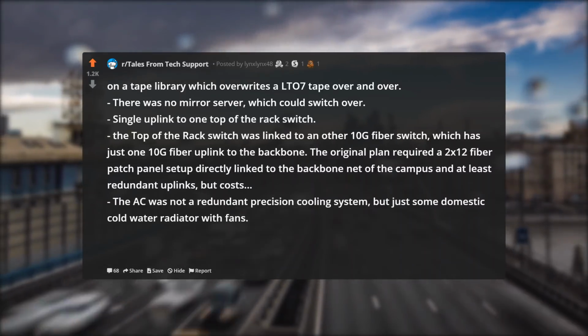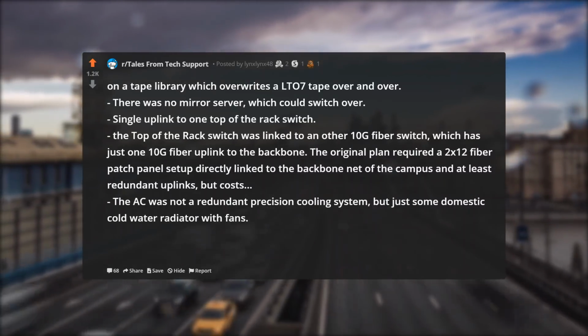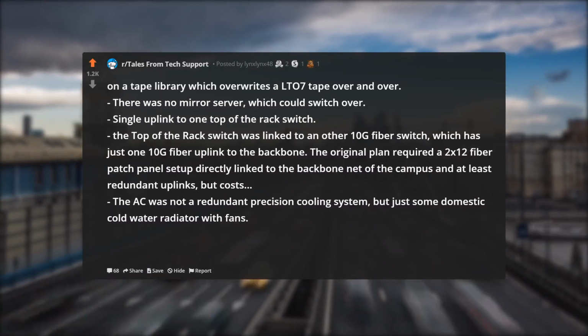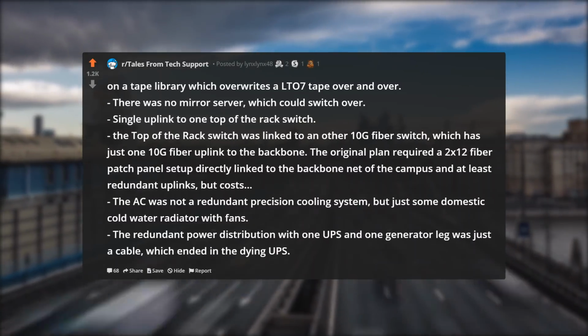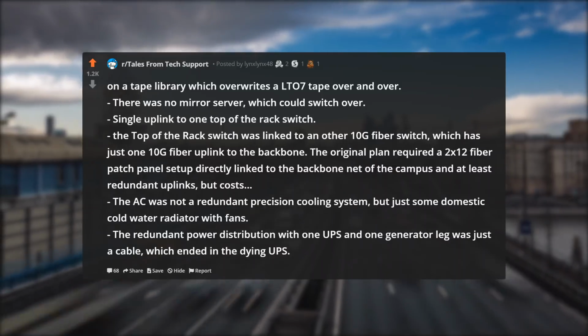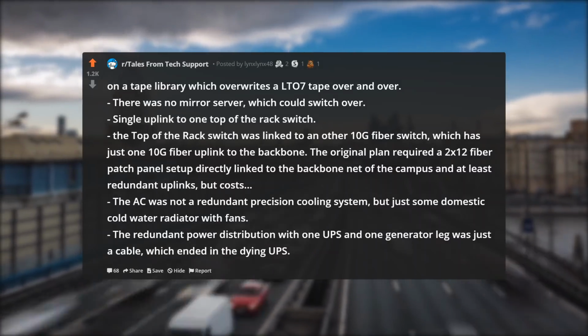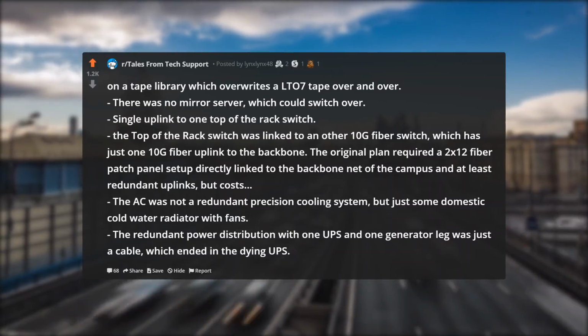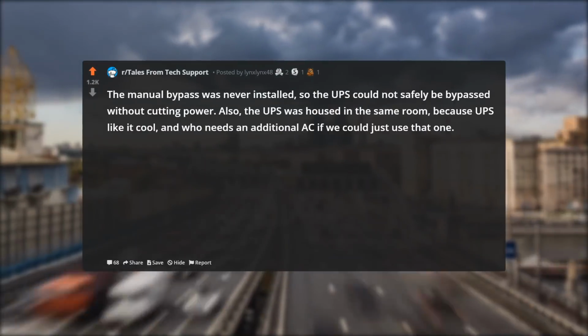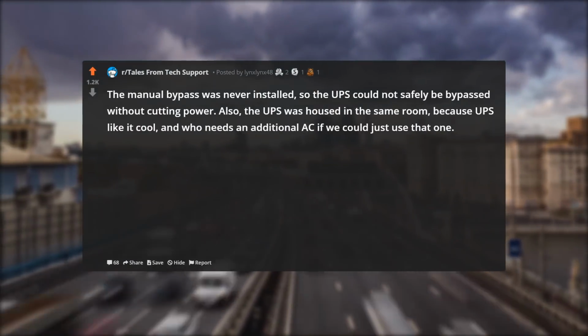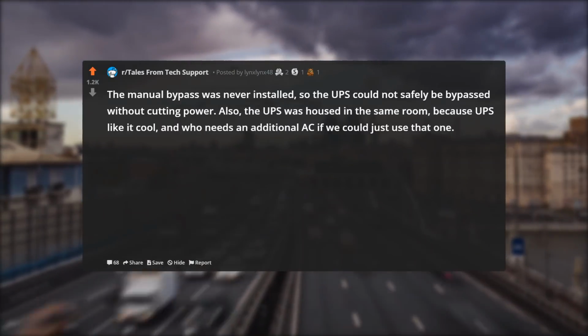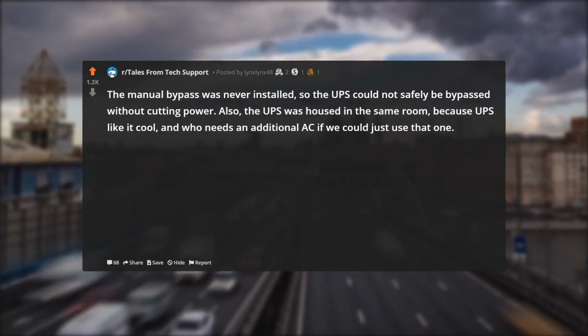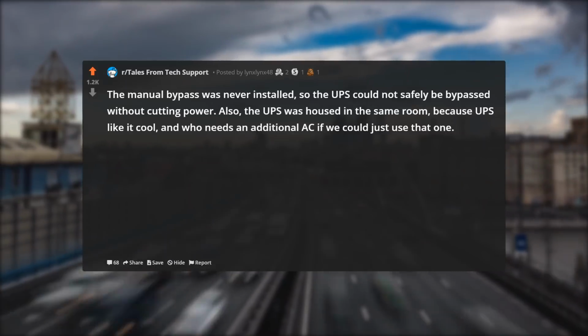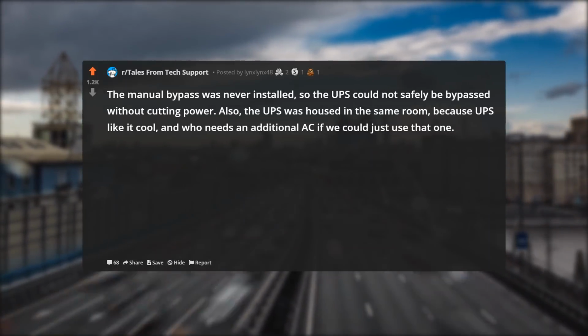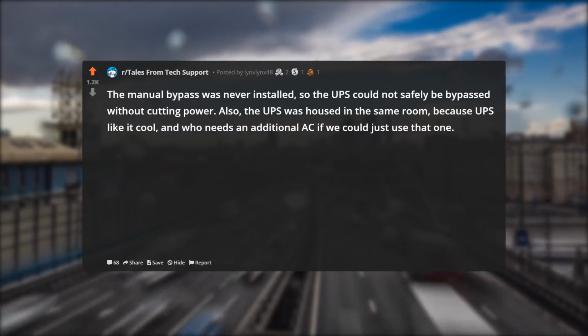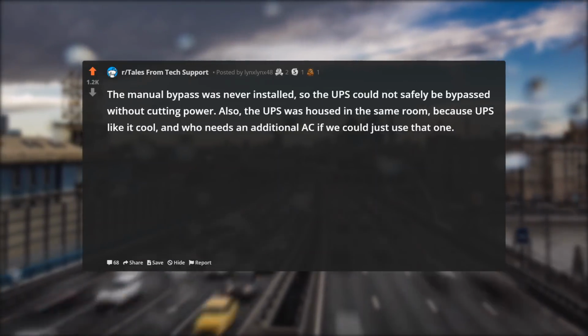The AC was not a redundant precision cooling system, but just some domestic cold water radiator with fans. The redundant power distribution with one UPS and one generator leg was just a cable, which ended in the dying UPS. The manual bypass was never installed, so the UPS could not safely be bypassed without cutting power. Also, the UPS was housed in the same room, because UPS like it cool, and who needs an additional AC if we could just use that one?